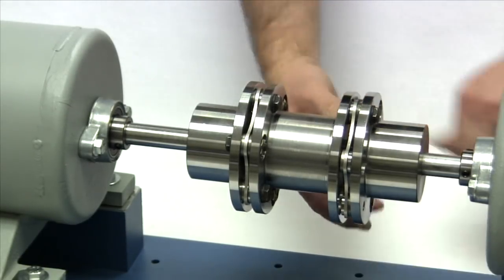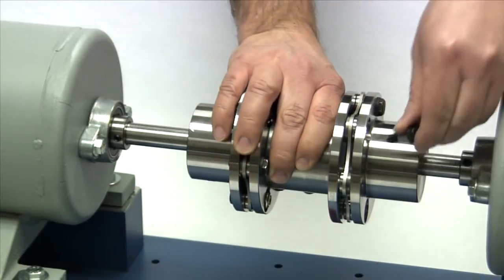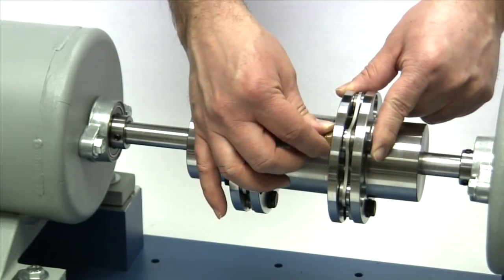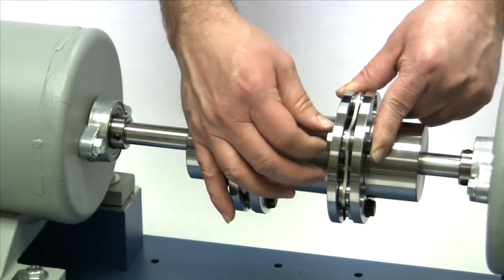When we tighten the bolts and the lock nuts, we will tighten all the lock nuts on one side of each disc pack, then the second side. Do this on one end of the coupling, then repeat on the other end.